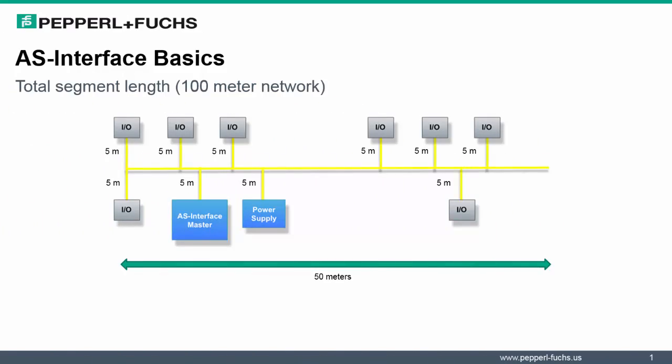A fundamental characteristic of an AS Interface network are the 100-meter segments. As a network is arranged, there may be multiple drops from the main trunk line down to the various IO modules. As these drops are calculated, they cannot exceed the 100-meter limit.